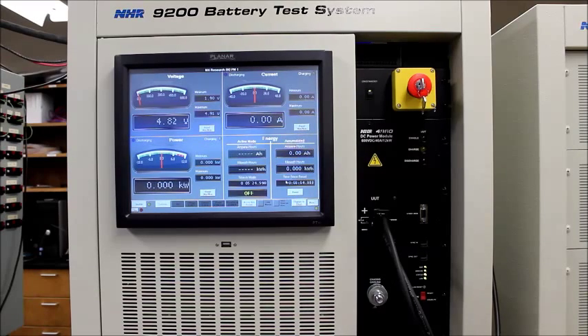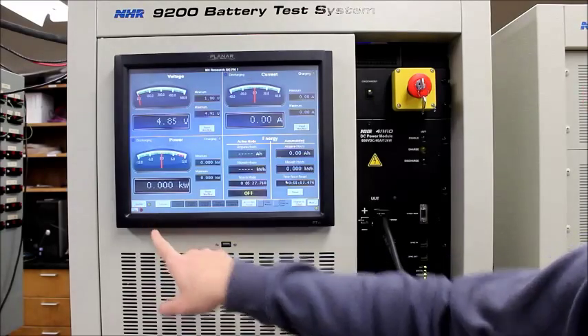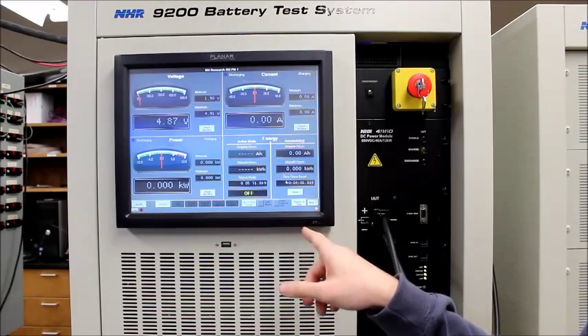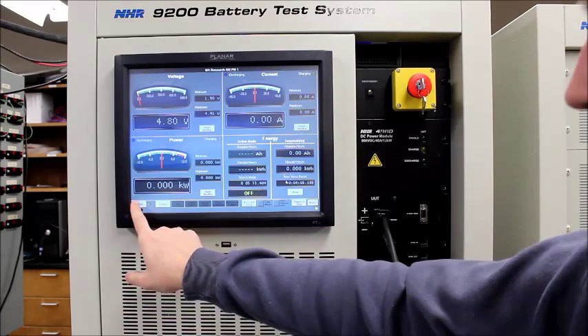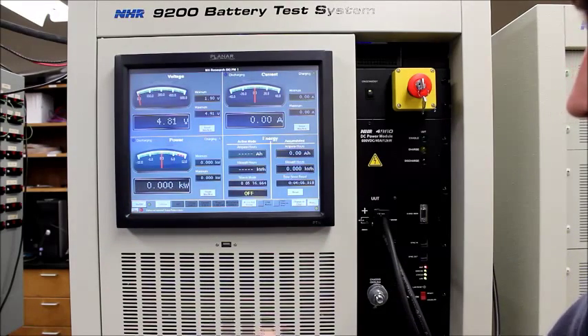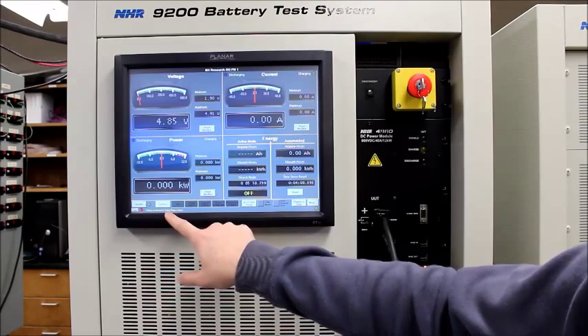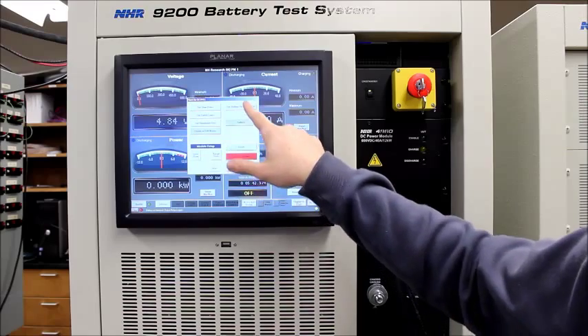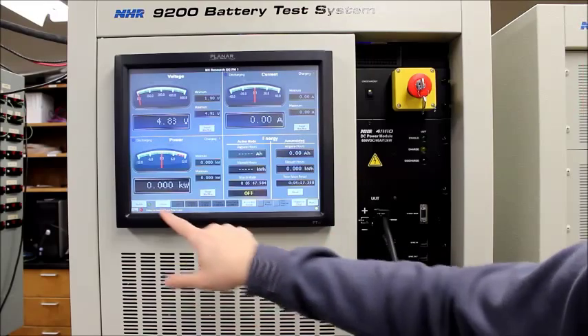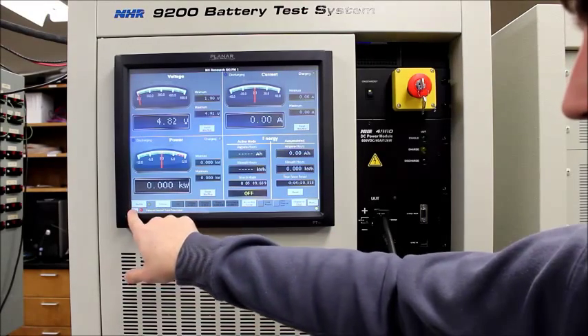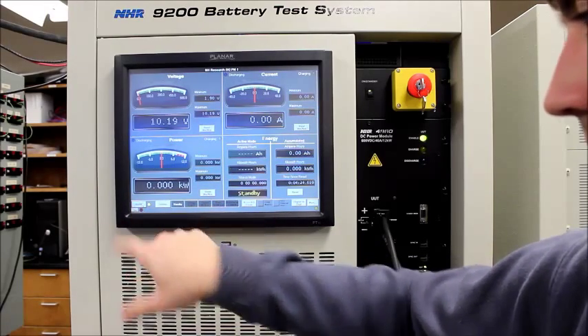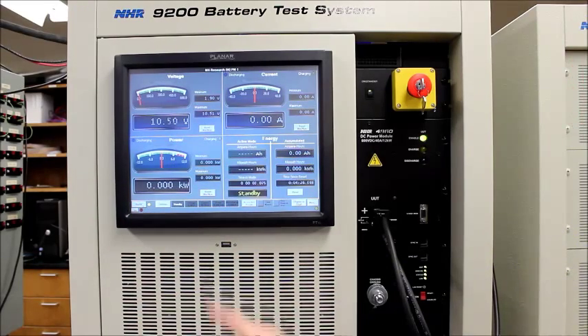Now that it's at the home screen, we can enable the output. We've already done the set battery voltage so we can turn it on. Push on/off. It says battery not detected, output relay is open. That means that this setting went back to its default. Set it back to zero. Let's try it again. I have to clear, push the clear button, and on/off again. Okay, now we're on and in standby.